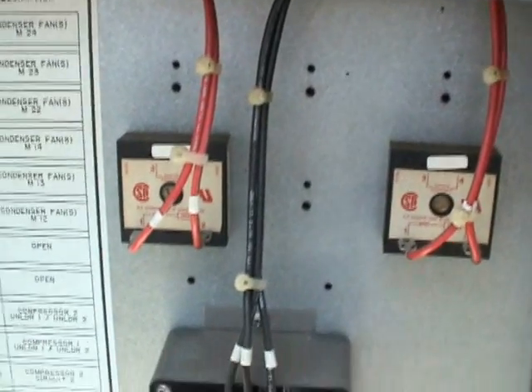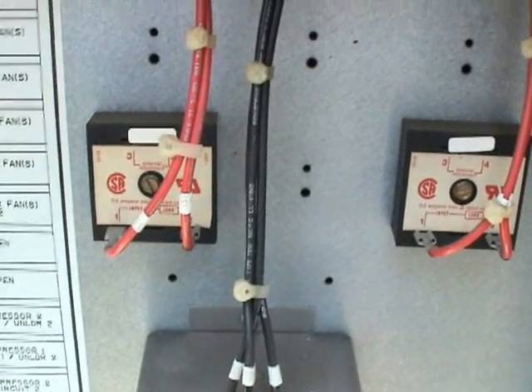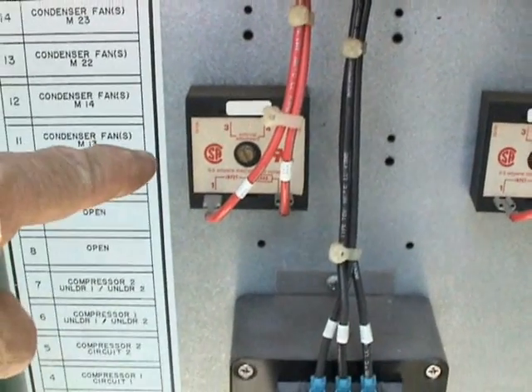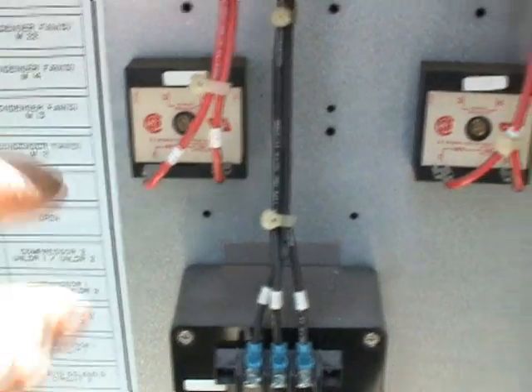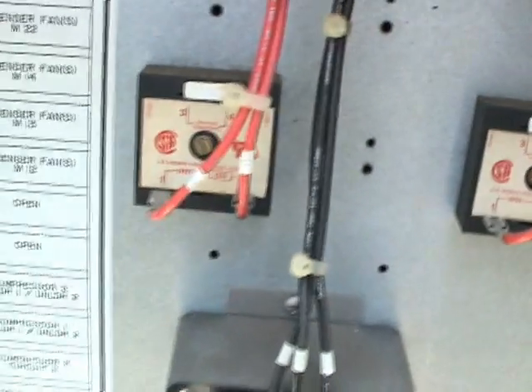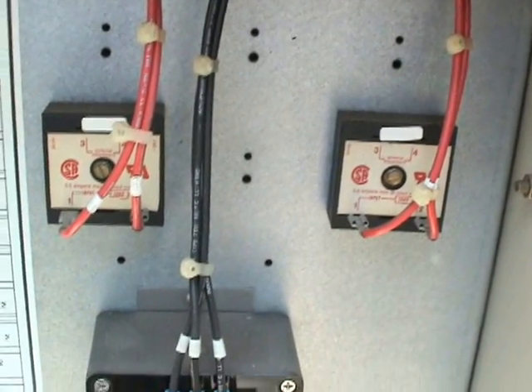Now in many cases the model and serial number on the system is going to be very important, especially in OEM products such as these time delays, like this one and this one. They're both actually different, believe it or not, and they're not really 5-minute time delays. They're more like 1 second or 25-second time delays, things like that.